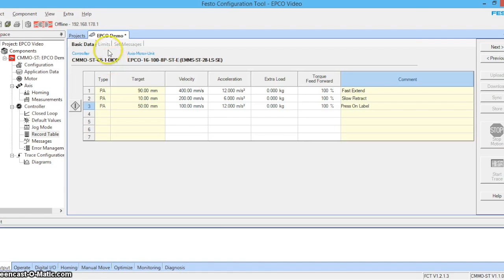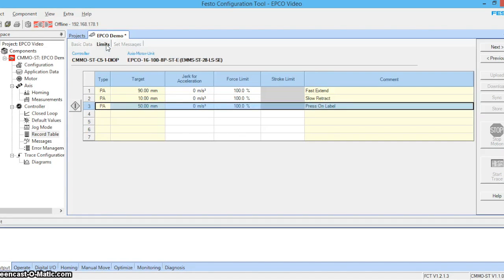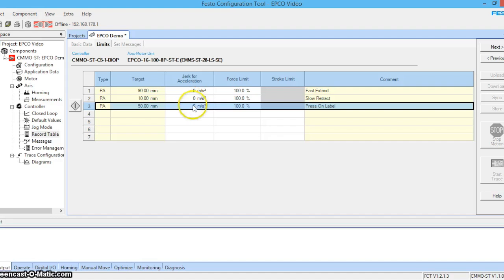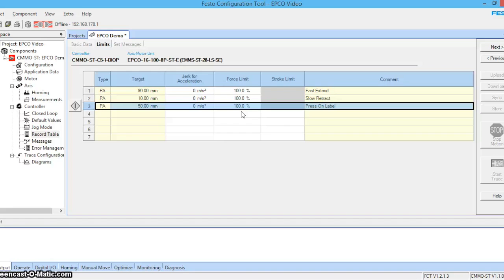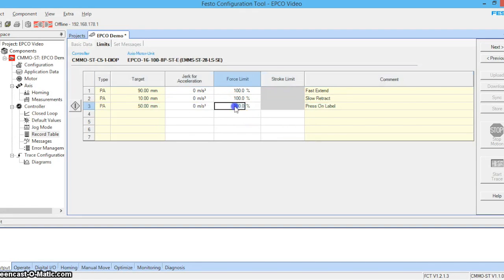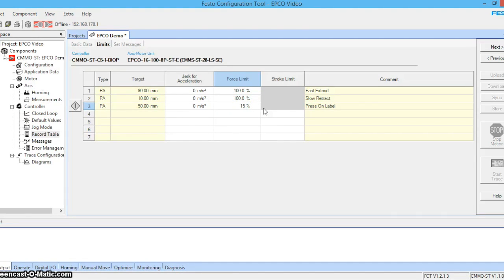Okay, next let's go into our limits tab. Where you can see our jerk for acceleration is left at zero. If a start stop motion is very jerky this value may need to be specified. Our force limits can be used to control how much force is applied when the actuator makes contact with an object. This can be used for pressing and clamping applications. Let's go ahead and reduce our press on label to 15%. Stroke limits don't apply in valve mode. Let's click next.